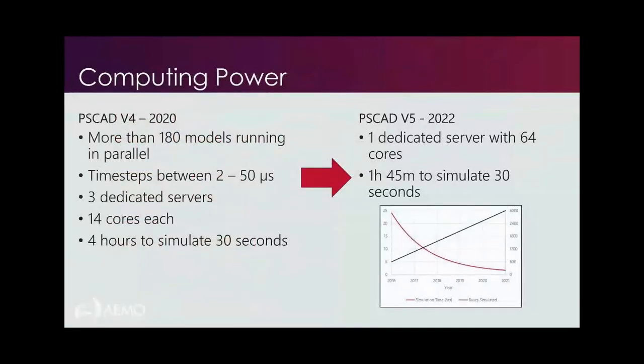The main disadvantage of electromagnetic transient models is that they are incredibly slow and computationally intensive. Before this year, we used PSCAD version 4, and our model consisted of 180 generator models running in parallel — as far as we're aware, the largest model in use anywhere in the world. All 180 generator models run with timesteps between 2 and 50 microseconds, which is incredibly detailed. The computational requirement was three separate massive computers with 14 cores each, and even then it would still take four hours to simulate just 30 seconds — very slow due to the enormous amount of detail in those models.